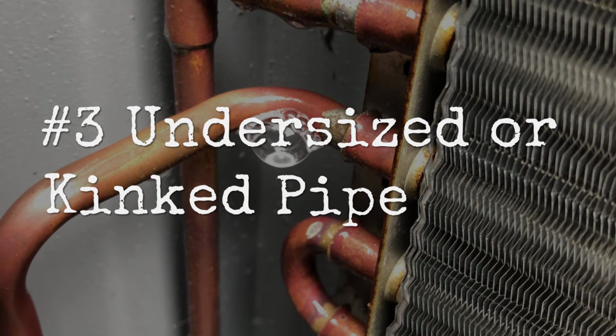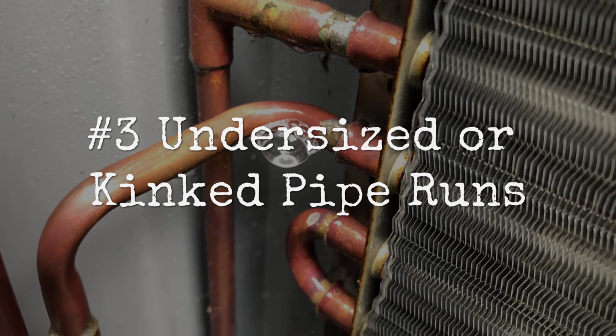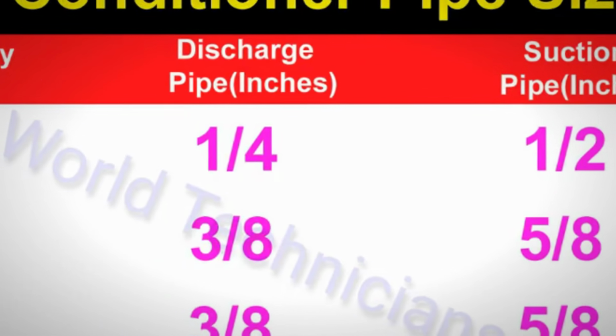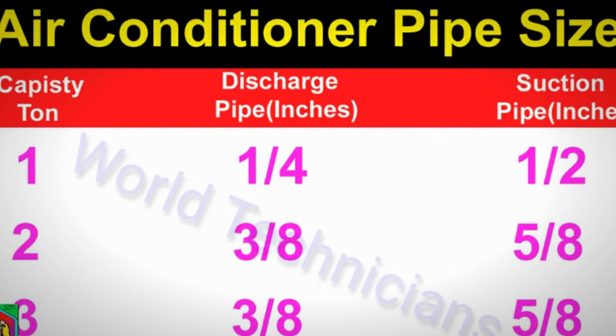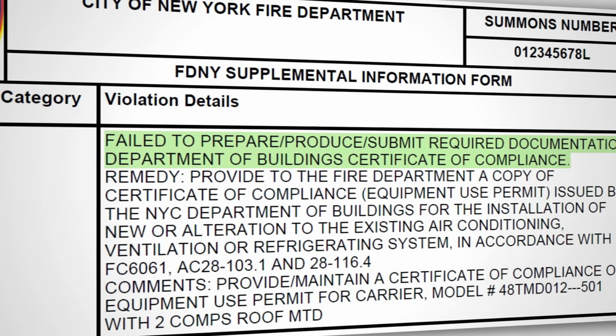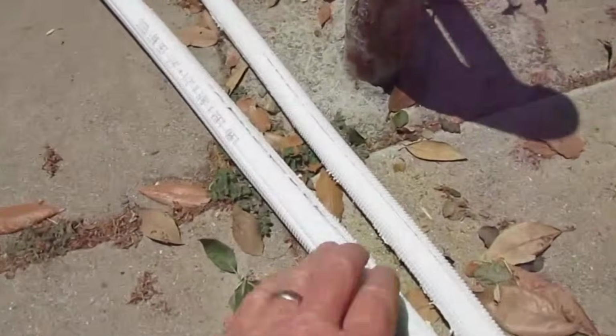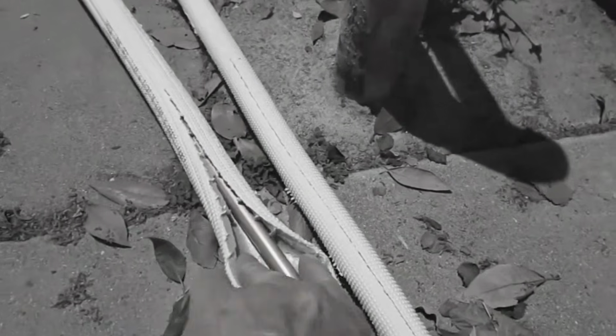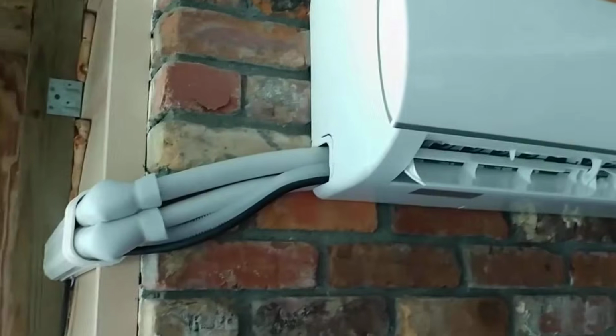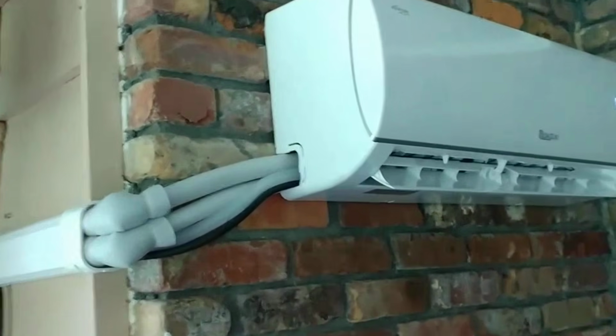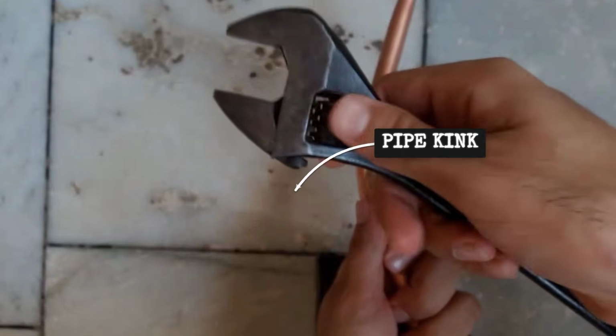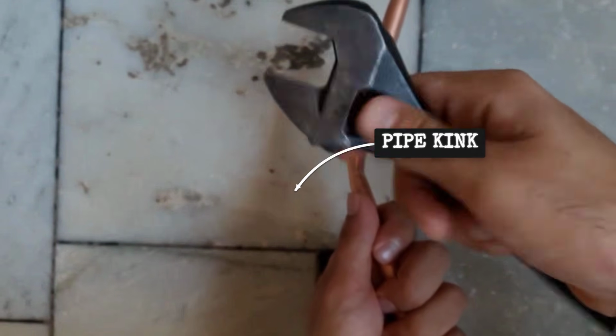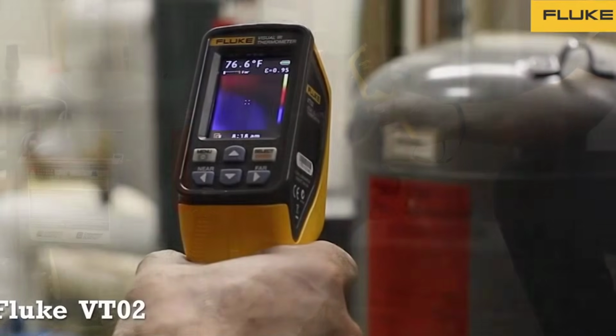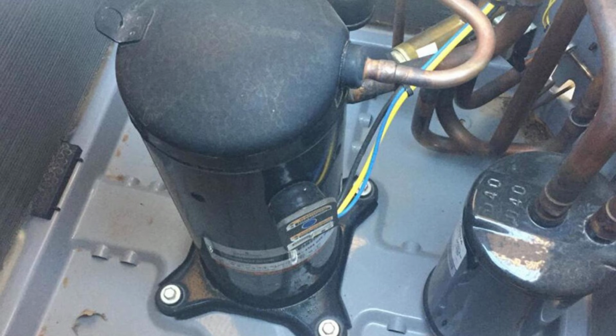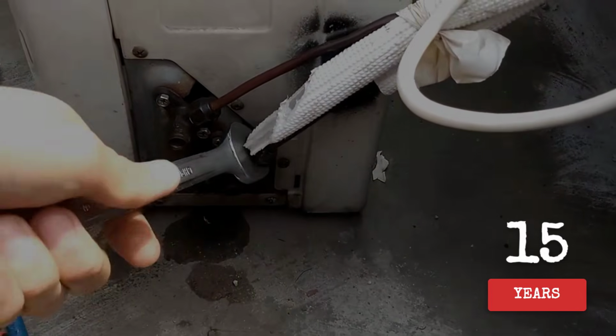Shortcut 3. Undersized or kinked pipe runs. The pipe diameter specified by the manufacturer for each unit size is not a suggestion. It is an engineering requirement. A budget installer who runs undersized pipe to use up stock from a previous job, or who routes pipe in a sharp bend to avoid drilling through a wall, creates a restriction in the refrigerant circuit that forces the compressor to work harder than it was designed to. Over 5 years, that extra load shows up as a dead compressor on a unit that should have lasted 15 years.